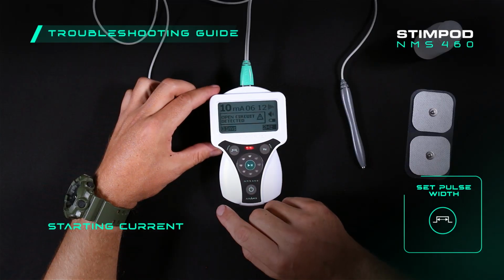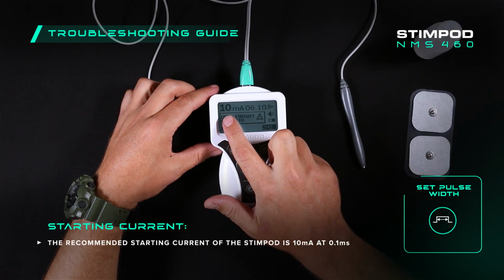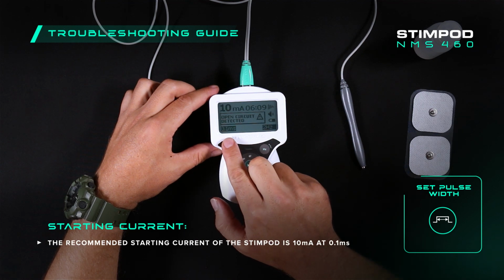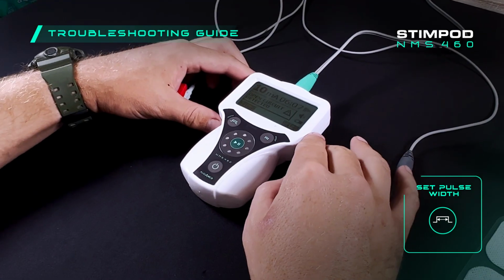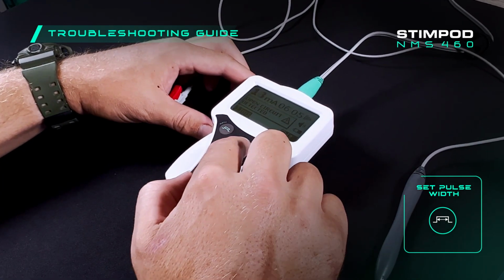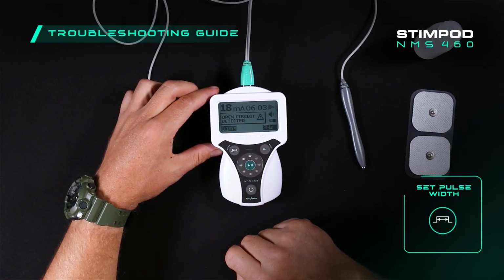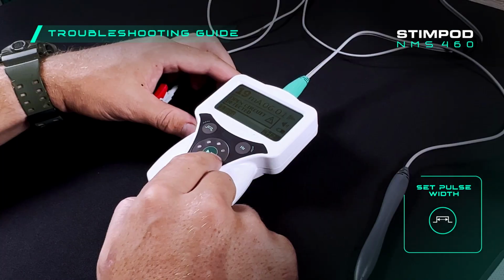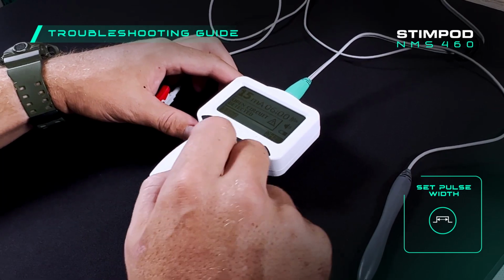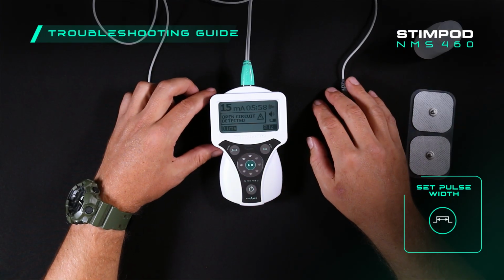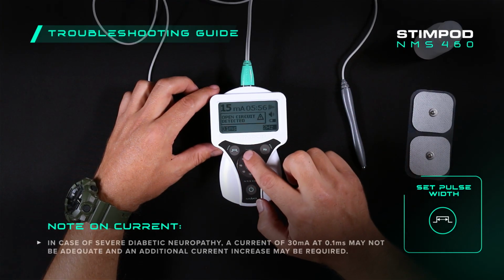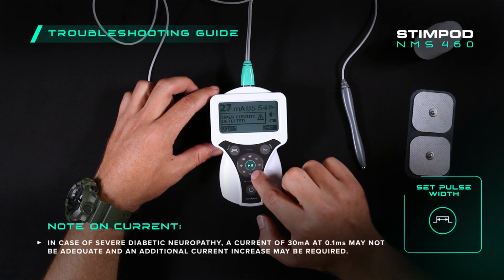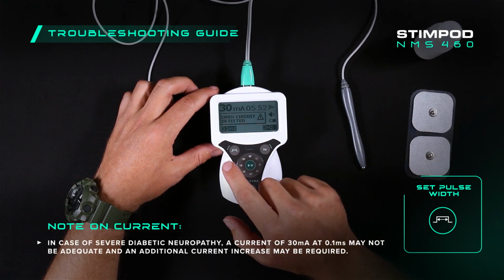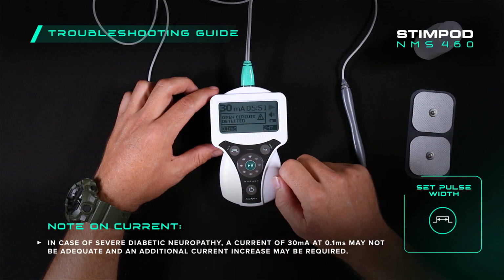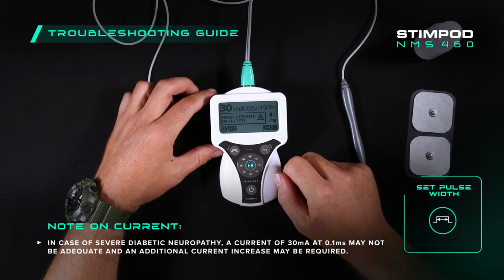When treating a patient with a Stimpod, it's recommended to start around 10 mA with a 0.1 millisecond pulse width. You can then increase the current to a level where the patient describes the sensation as a pinch. Then, reduce the current by a few milliamps until the patient describes the sensation as a tap. In cases of severe neuropathy or nerve damage, you may find that 30 mA at a 0.1 millisecond pulse width is not enough.